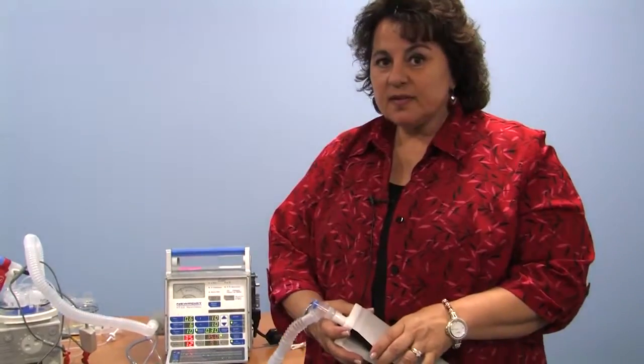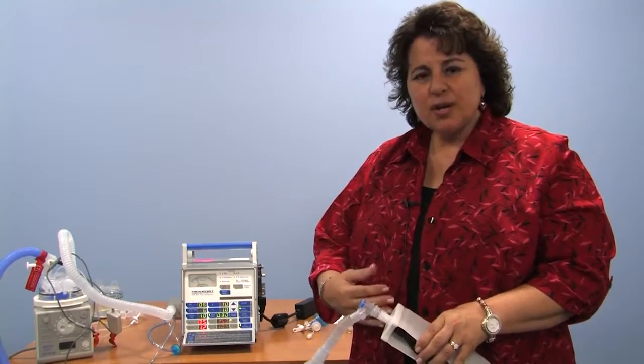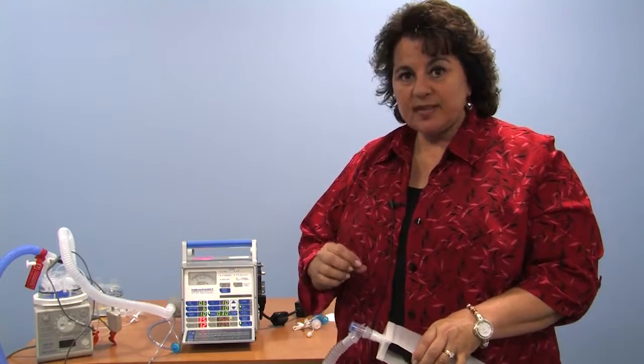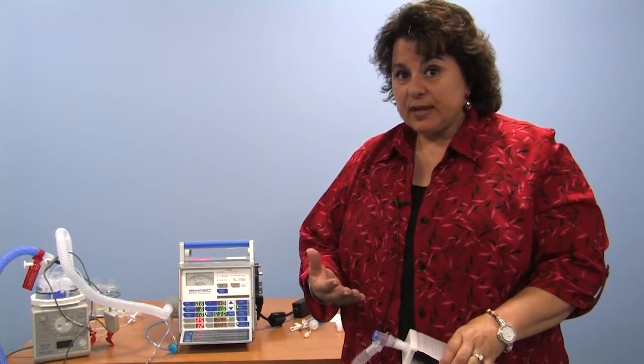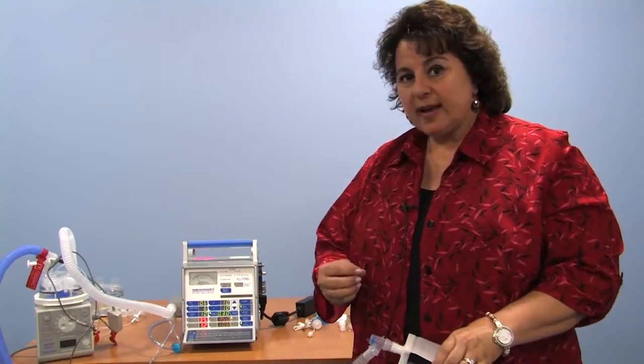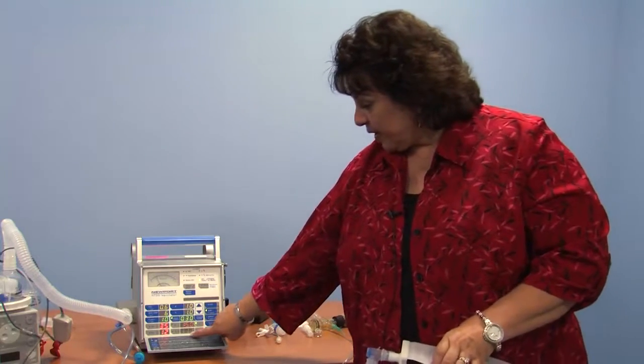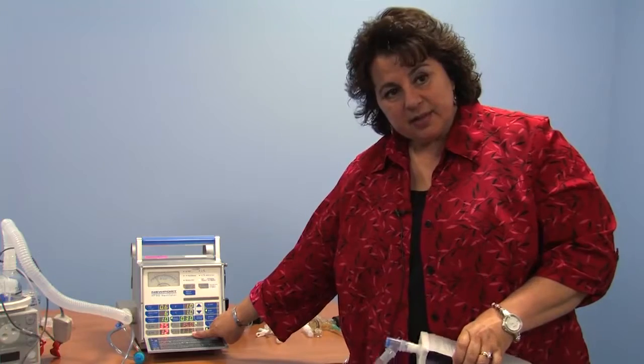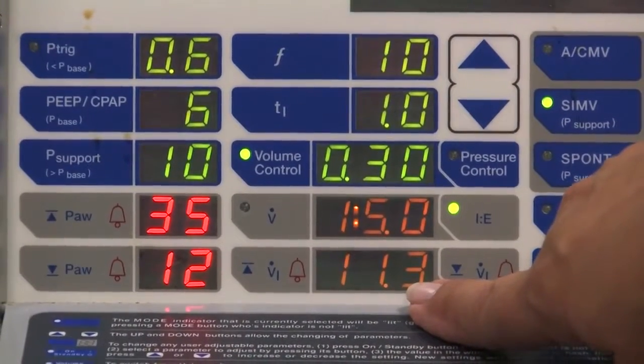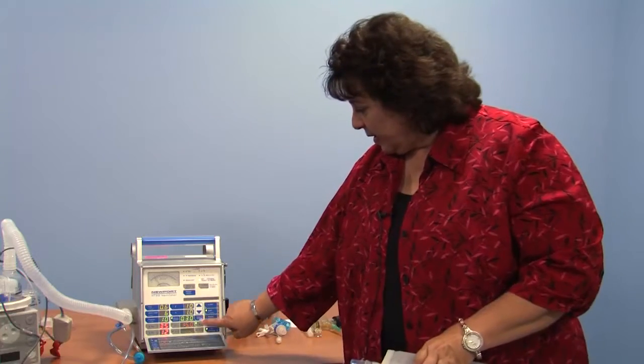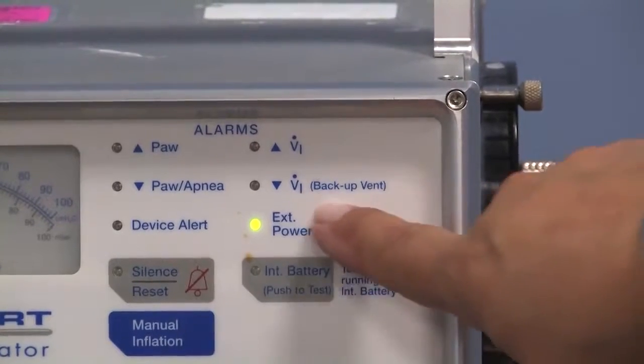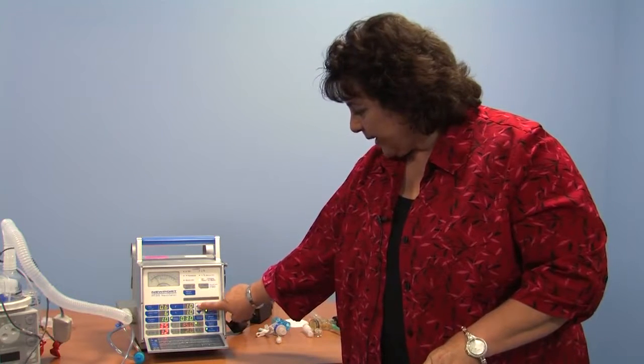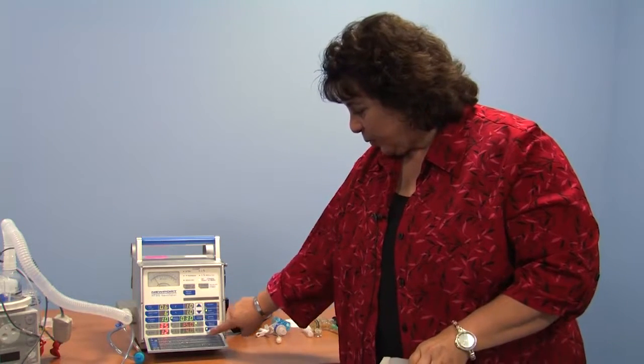The Newport HT50 does provide backup ventilation for those patients that are not on a mandatory rate, in which the rate's going to come along anyway. For example, if your child's on CPAP or pressure support and doesn't have a mandatory rate, what happens if they stop breathing? Some of you know the word apnea. This machine actually looks at low minute volume as a reason to give more breaths. So what it looks at is the amount of air. We've talked about minute volume. Right here we see 11 liters a minute is what our patient is breathing right now, and our low alarm is set at 2. Up here you'll see low VI alarm is hooked up to backup vent. So if I raise our alarm past the 11, the machine will think that we're not breathing enough and go into what's known as backup ventilation.